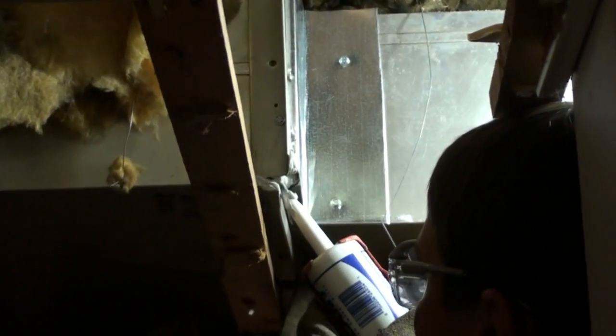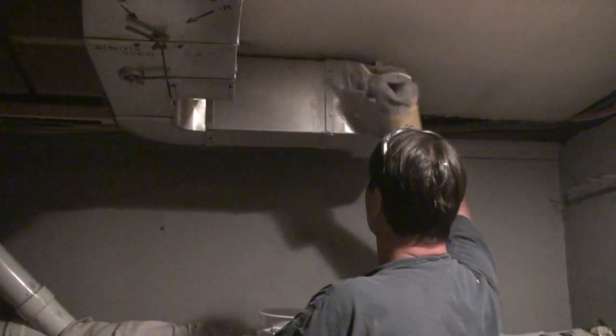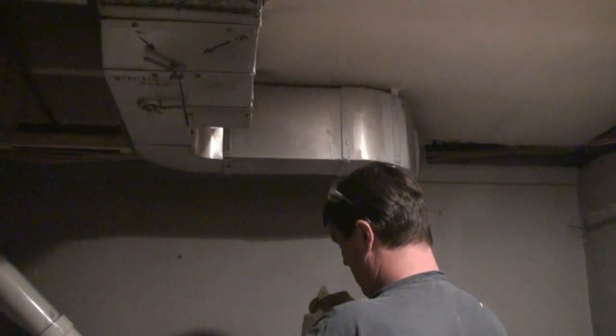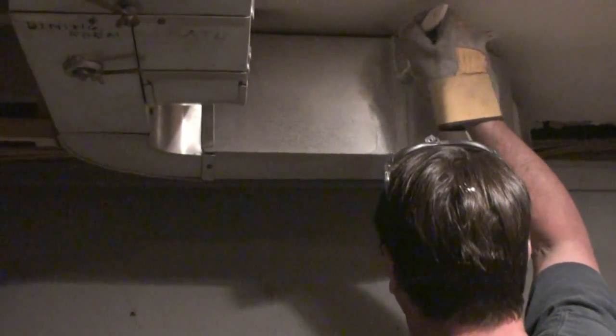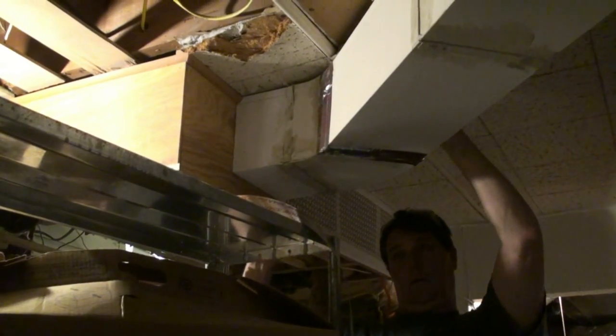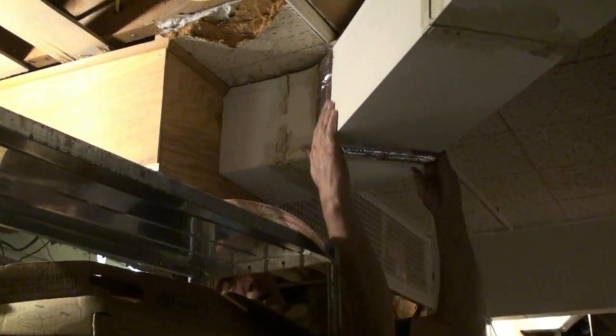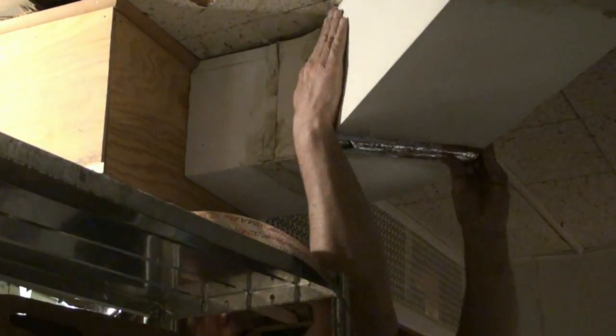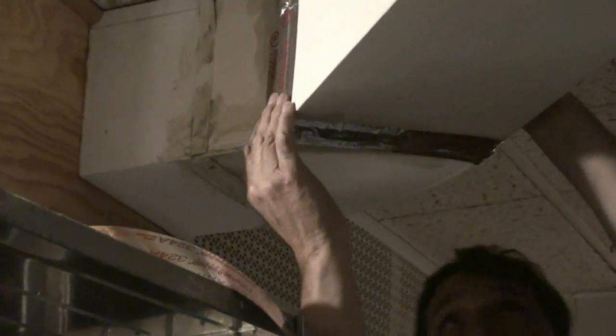And then we proceeded to use some mastic to seal every seam on all the ducts. Every junction where sheet metal is bent or goes into another straight run, every seam has to be masticed up. That's a water-based mastic, low VOC. So there's no environmental or health issues. And then on top of that, we use a UL 181 aluminum tape to bond with the mastic and get a good bond and seal on all the seams.